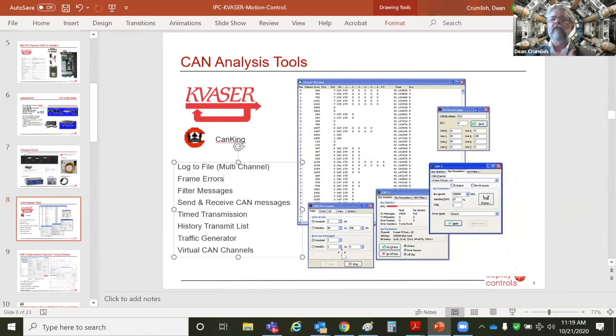I say if you see one frame error, you have to ask, why did I get even one? Did I have a bolt of lightning? Am I arc welding? Did I forget to put the terminator in? So CAN is very forgiving. It will let you run the system without your terminator. It's not a good idea. You should have 0 frame errors over time, unless there's a bolt of lightning.